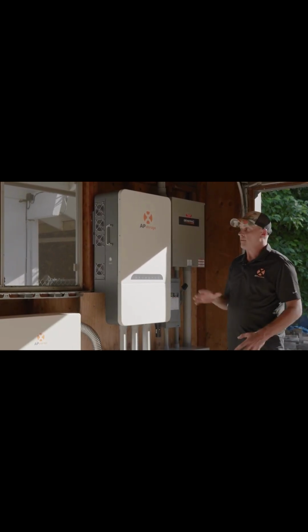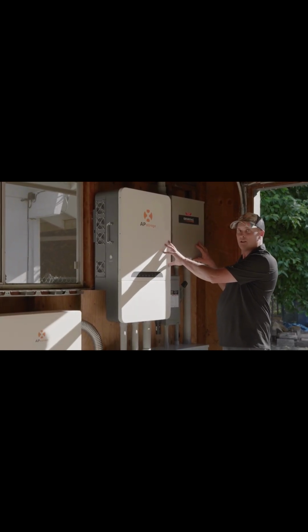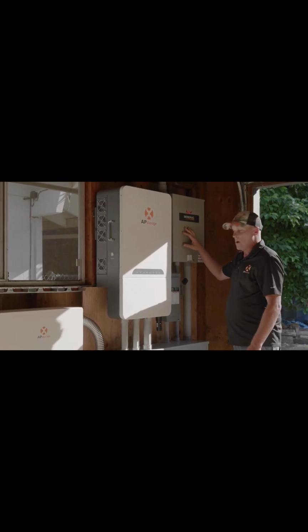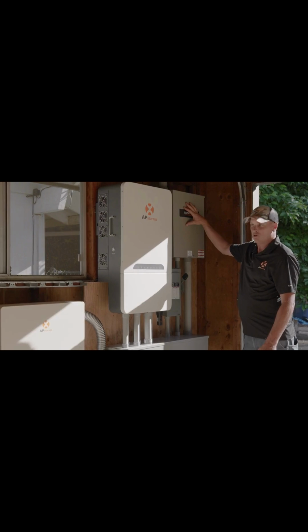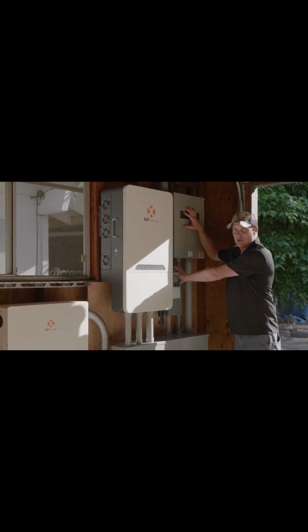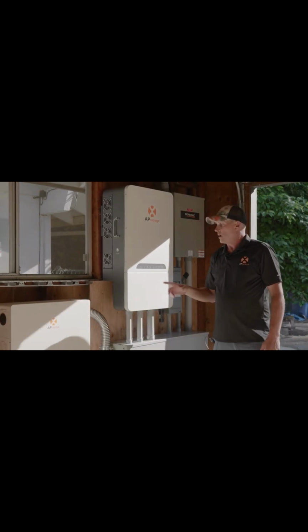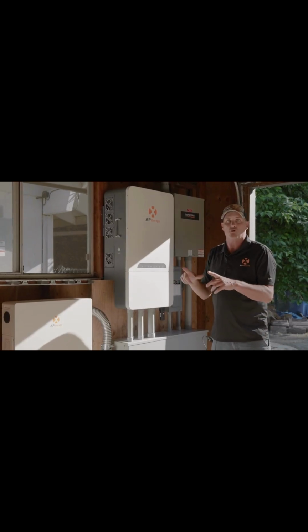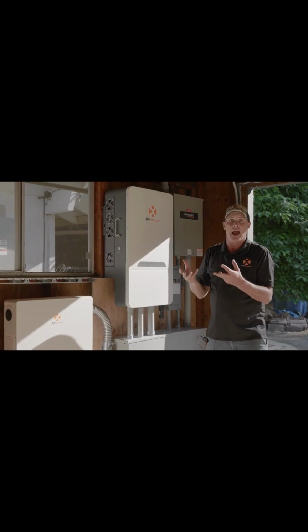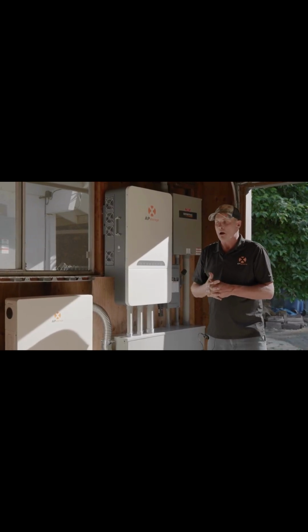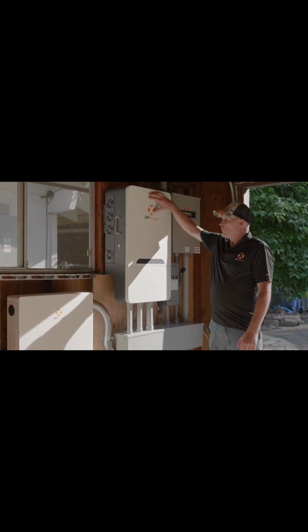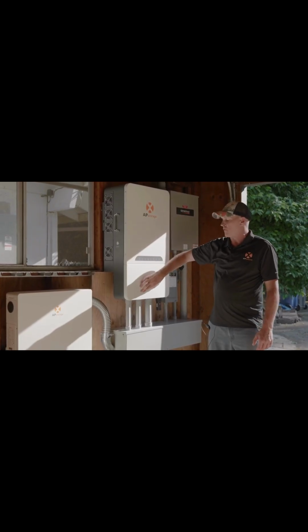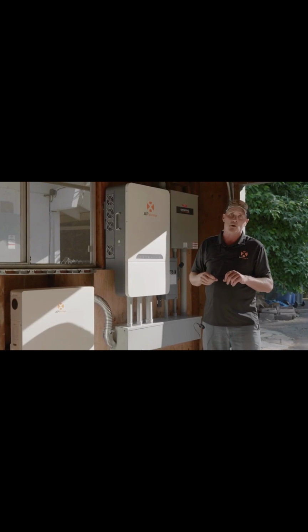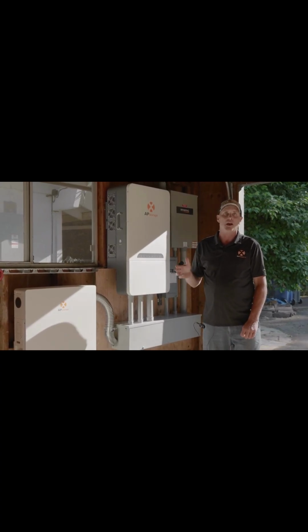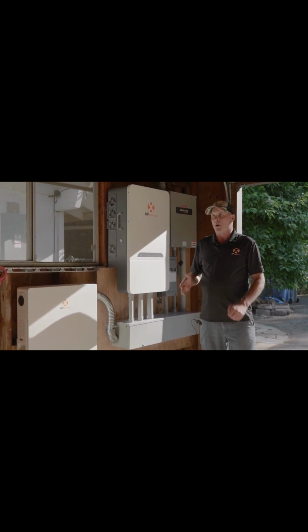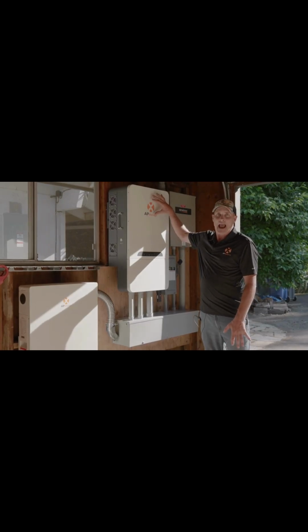Now it's important to know that this is one way that you can wire this system with an automatic transfer switch in it. We could take away this automatic transfer switch and this line side tap with this 60 amp fuse disconnect, and we could do what you normally do. You take the grid side of this, connect it to your 200 amp electrical panel. Maybe that's done by a line side tap if you're running out of ampacity in your panel. But if you do it that way, when the grid goes down, the off-grid output from the PCS will go to a traditional backed up loads panel that would contain all of the circuit breakers that you want to have power when the grid is down. So when you're using a backed up loads panel, the PCS acts as your transfer switch.